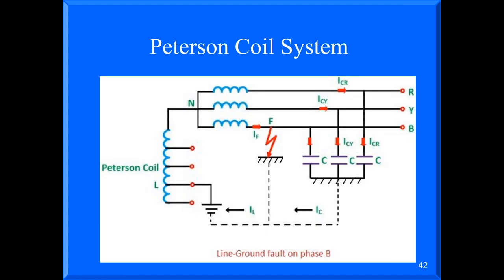So basically, I've made it a pure ungrounded system. Okay? So you're going to go, that's interesting. How do they find the ground? Or what happens if there's a ground? To do that, because this capacitance is changing, I've got to be continuously changing this inductor.